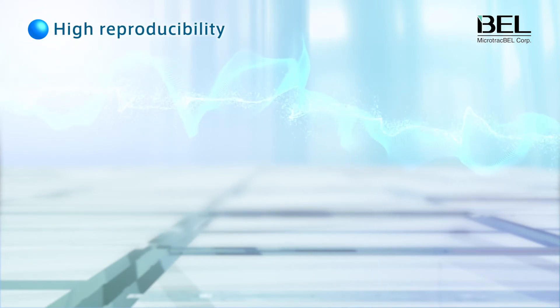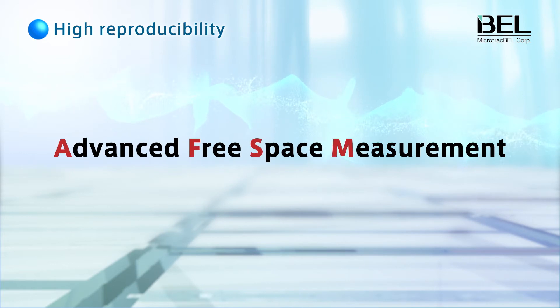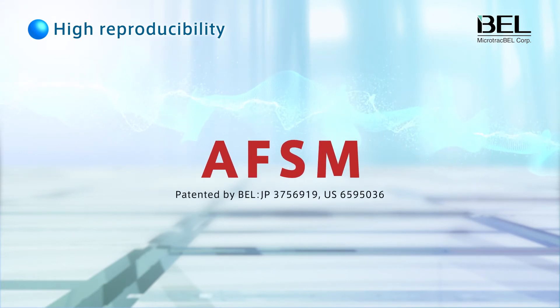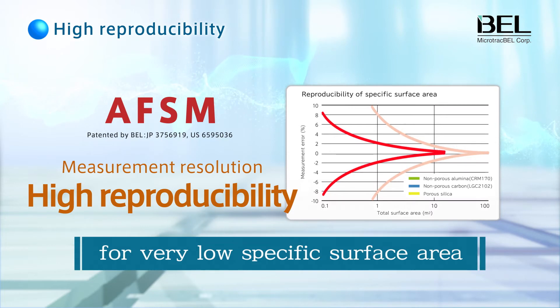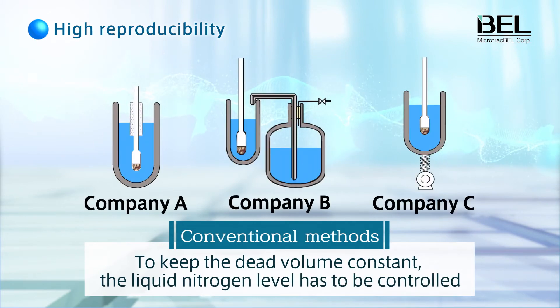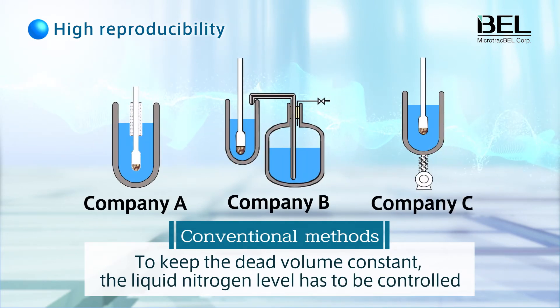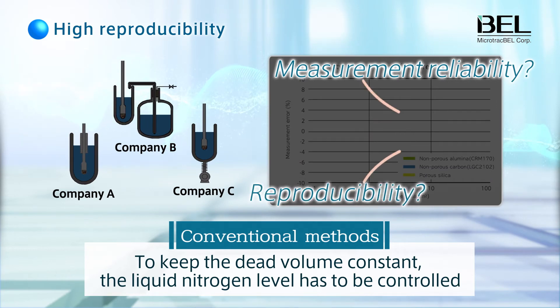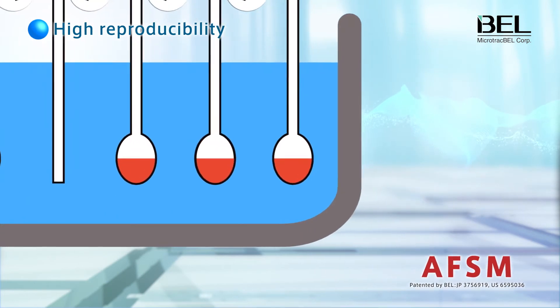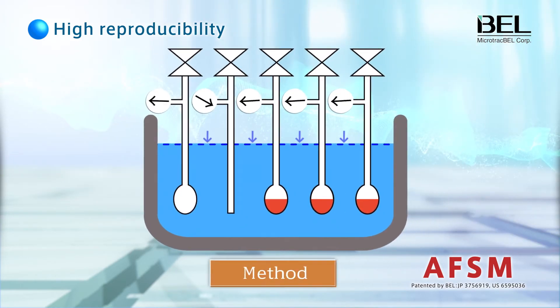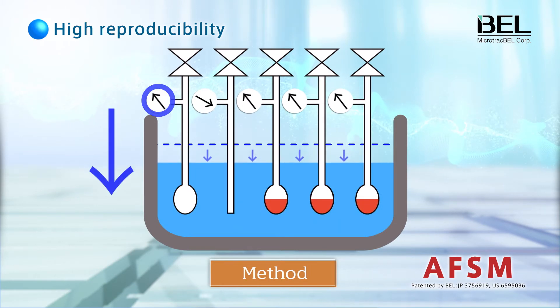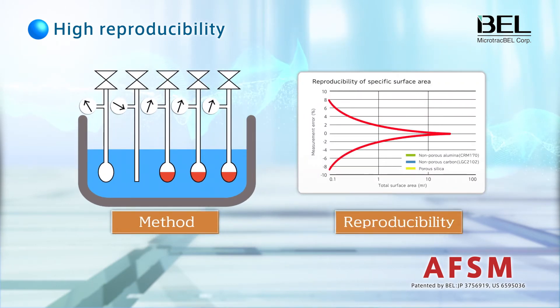The patented Advanced Free Space Measurement, or AFSM, is our cutting-edge technology. High accuracy and reproducibility can be achieved for very low specific surface areas. Conventional liquid nitrogen level control has accuracy and reproducibility issues. Our advanced free space measurement avoids this problem by compensating for the change in the free space in the sample cell due to liquid nitrogen level changes. The free space change in the sample cell can be corrected continuously from the pressure change in the reference cell.